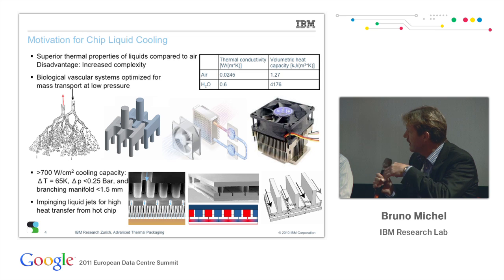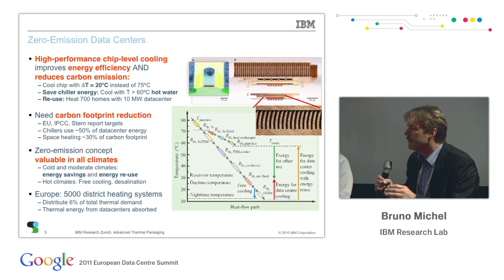PUE 1.05 plus the electrical delivery. Next slide. So we have shown that we can implement that based on a design that has been done for an air-cooled unit. We ripped off all the air cooling components and added a liquid cooling. And by that, we reduced the overall thermal resistance from the transistor to the mobile medium that transports the heat. In a data center, this is 75 degrees from the transistor to the cold air.